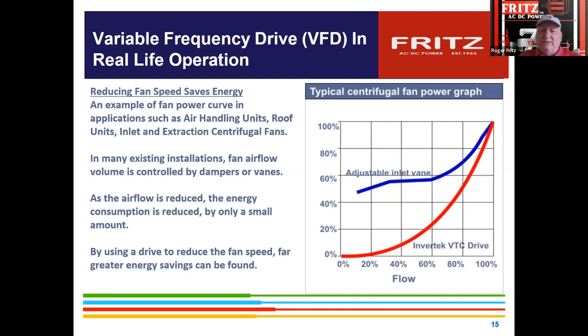And what's happening in Europe is a lot of the motors now, they've also figured out that when you put a VFD on a regular induction motor, at anything below 70%, the motor efficiency starts decaying. So over there, they're in version 4 of premium efficient motors, where they actually have permanent magnet rotor motors. And we're actually getting a lot involved in implementing new permanent magnet motors. That's similar to what the ECM motors are. Those are a DC motor that's rectified power from AC, with controllers on them.